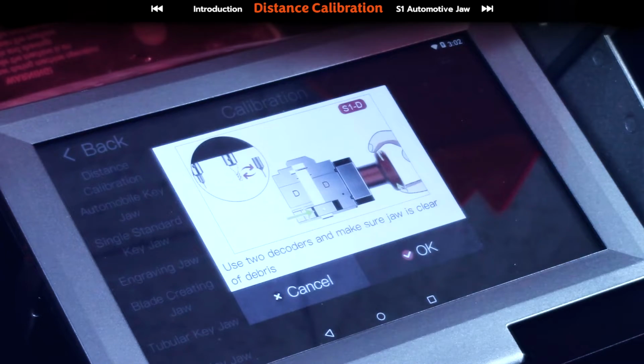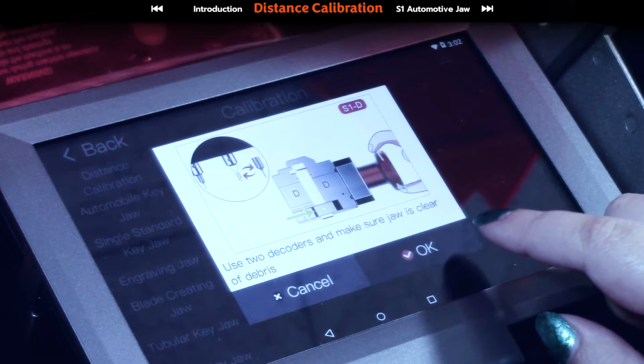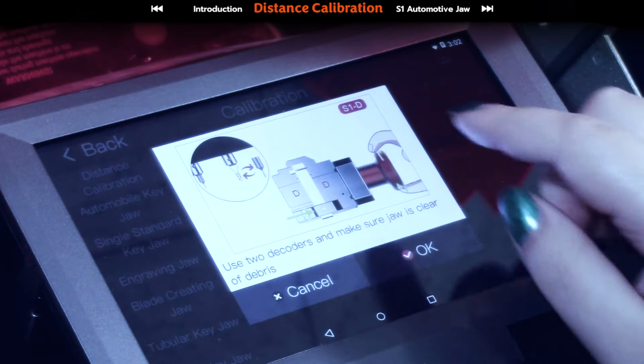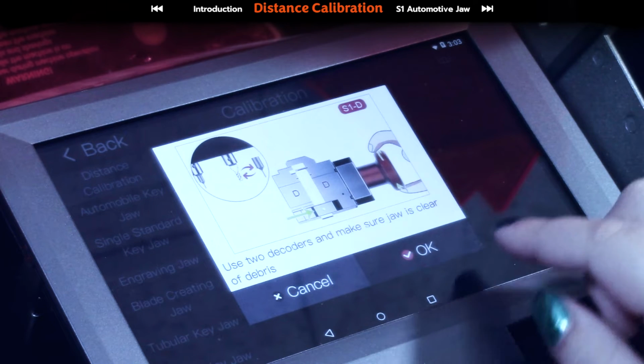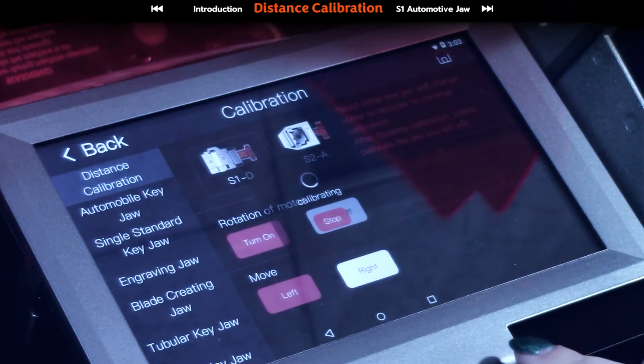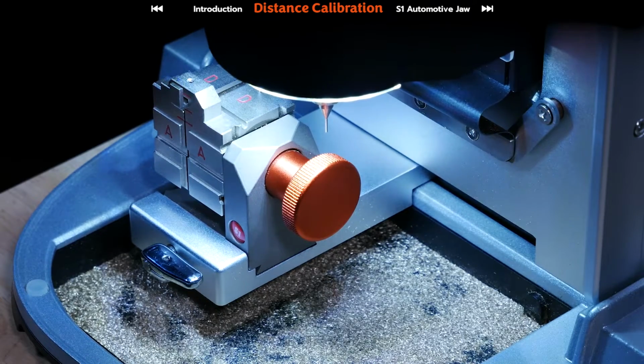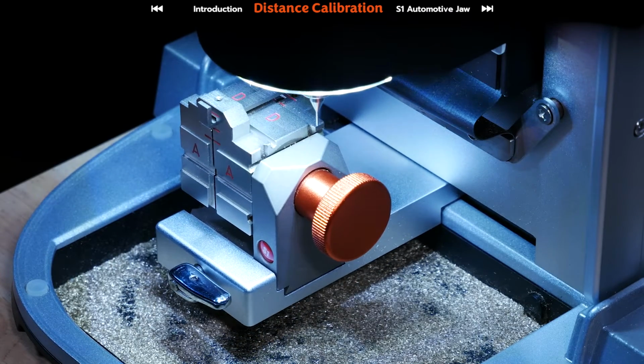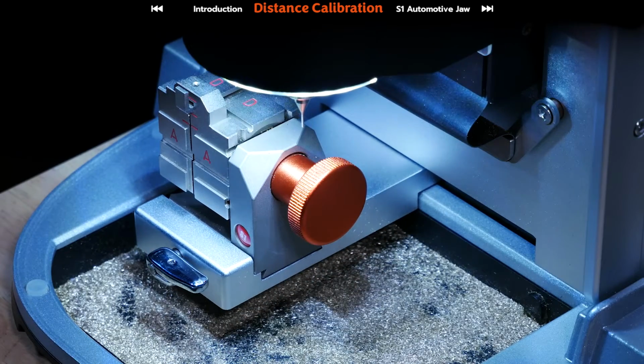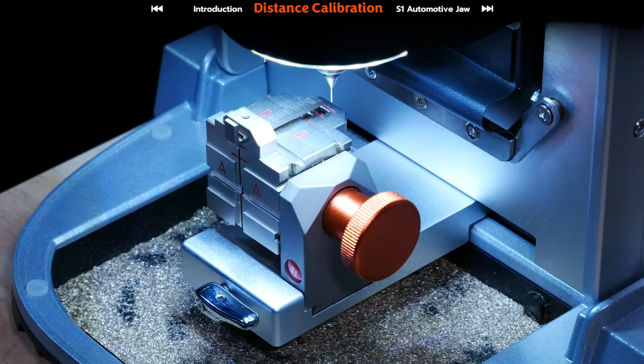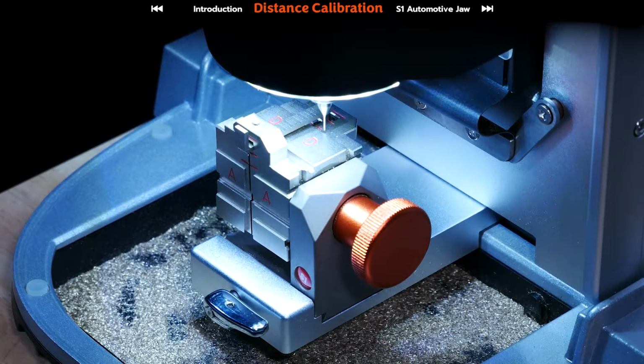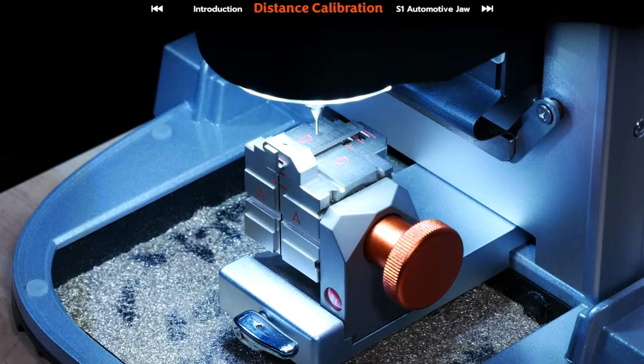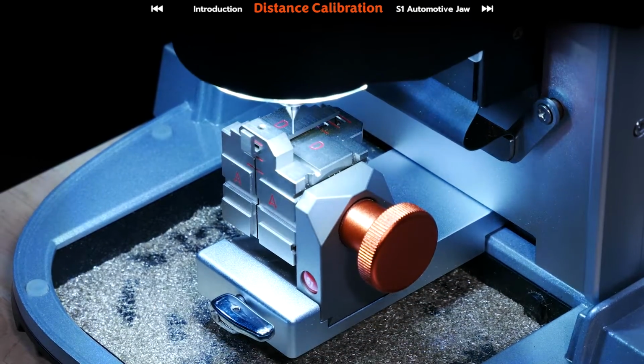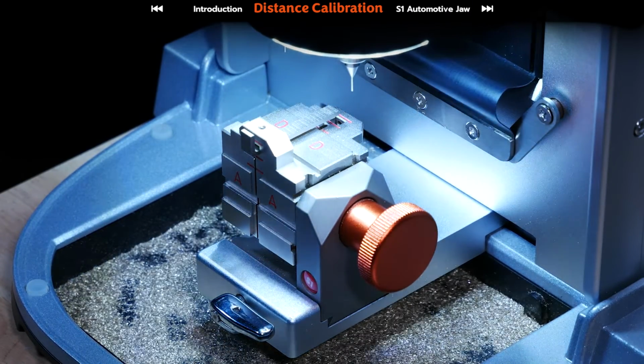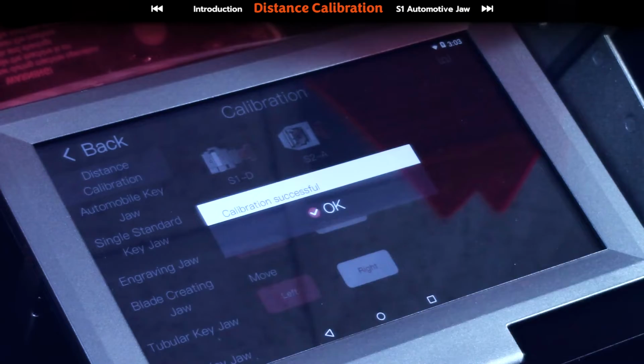And that is good. So now back up to the screen here, we're going to go ahead and just reference, double check. We have our two decoders in, lined up to the second red line. Tightened up, no debris on the jaw surface, hit OK. Calibration successful, hit OK.